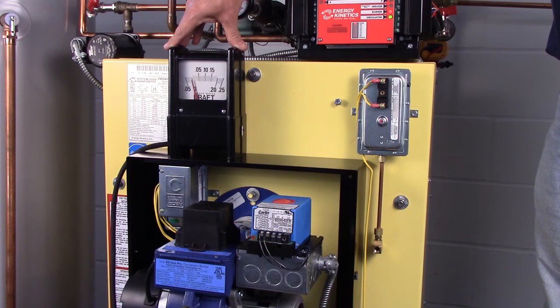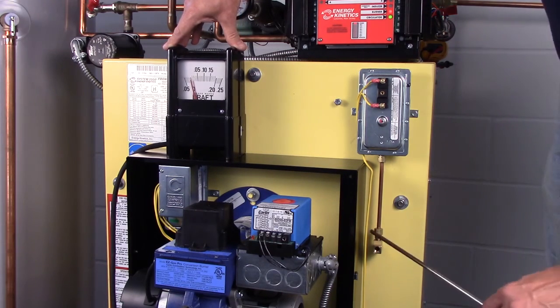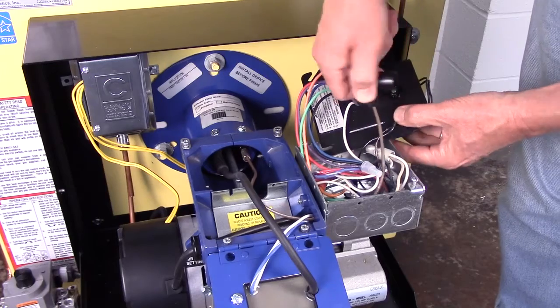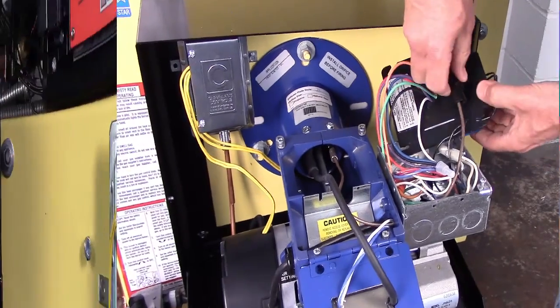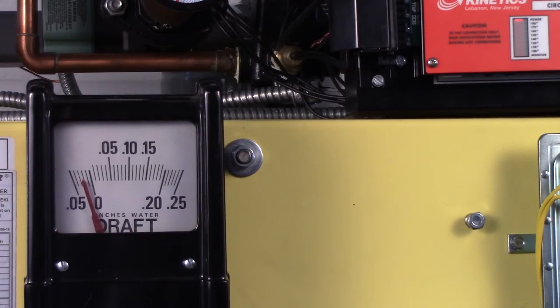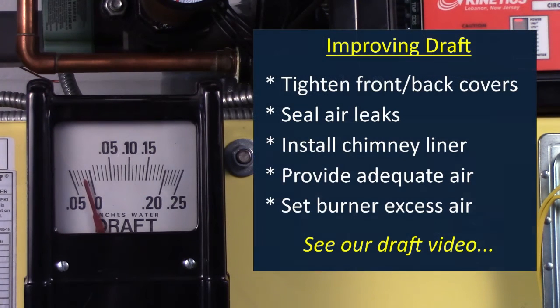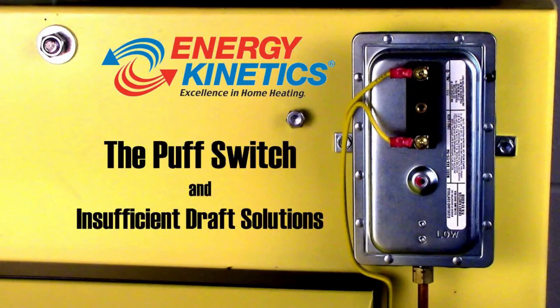Some other factors that can cause the burner to lock out after TFI include poor draft and an insufficient flame signal. With poor draft, excessive positive pressure over fire during the burner pre-purge or immediately after the light off may cause the blocked vent switch to open the gas valve circuit, resulting in a lockout. To improve draft, tighten the front and back boiler covers, seal all air leaks into the vent system, install a properly sized chimney liner, provide adequate air for combustion, and properly set the burner excess air, just to name a few items. See our video on draft solutions for more information.